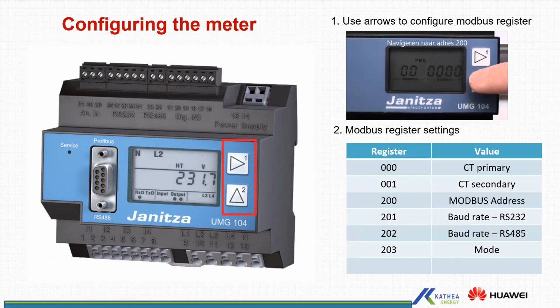So this is basically the UMG104. You need to set your CT ratios, primary and secondary. You need to set the Modbus address such that the system will be able to communicate with the logger. You need to set your baud rate. The default baud rate for all HUAWEI devices is 9,600, so you would need to set your baud rate to 9,600. And then the mode of communication, whether you are using TCP or RTU. Mainly it's RTU, which is RS-485. You need to set it as RS-485.